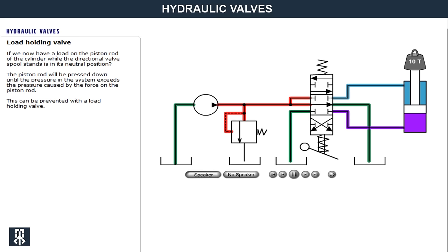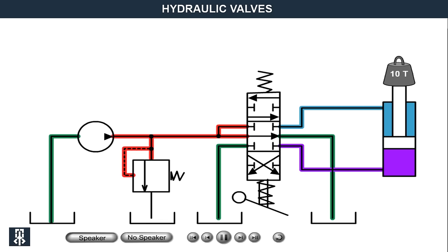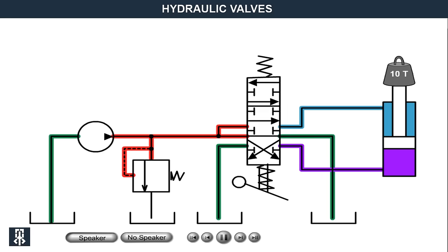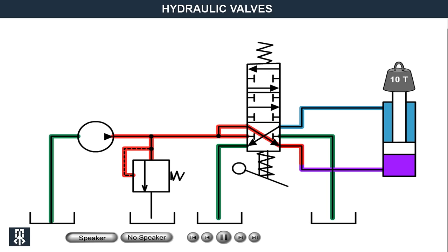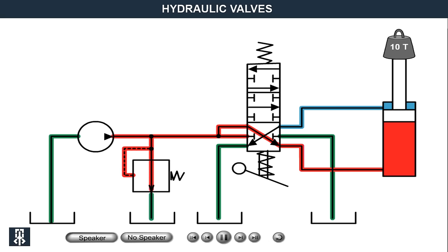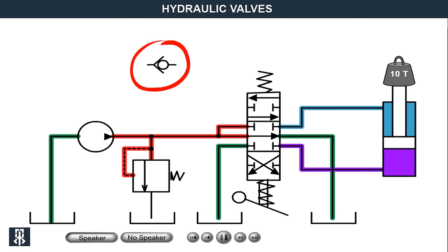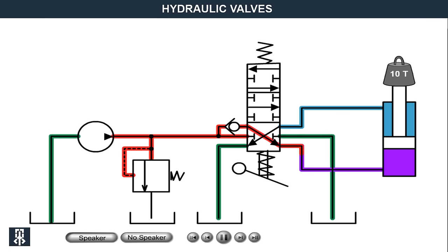If a strong force loads the piston rod when the directional valve stands in neutral position, and we try to lift the load by changing the directional valve position to connect the pump with the cylinder's plus side, the higher pressure on the right side of the directional valve and internal leakage in the pump results in oil beginning to flow towards the pump. This causes the piston rod to be pressed down until the system pressure exceeds the pressure caused by the force on the piston rod. This can be prevented with a non-return valve, called a load holding valve, placed before the directional valve — it holds the load until pressure from the pump side exceeds the pressure on the cylinder side.